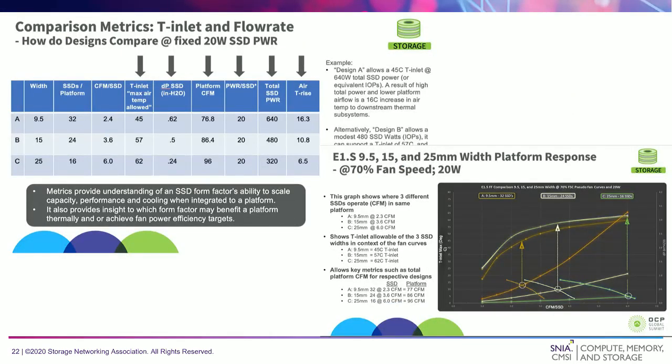Which brings me to, if you are interested in this, our Intel expert on the subject matter, Paul Gwynn, gave a great talk at the OCP about thermal methodology for EDSFF in actual servers. So looking at the 9.5, 15, and 25 millimeter symmetric and asymmetric enclosure options for EDSFF, and looking at the different power, different airflow, and different platform impedances, and what the actual power and airflow requirements would be. If you guys are interested in the thermal capability of EDSFF, I can point you to that presentation.